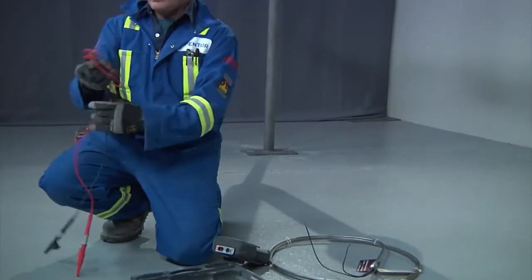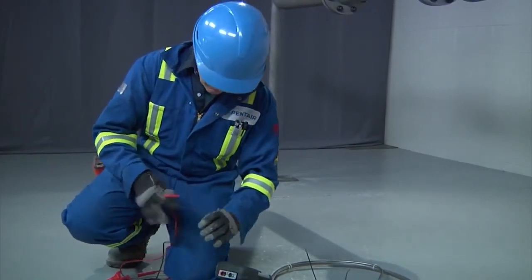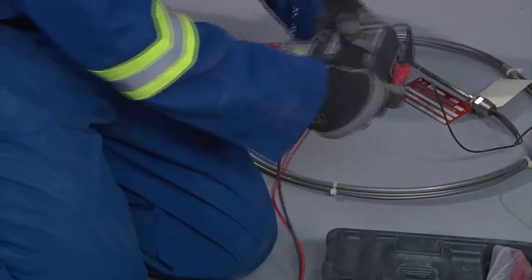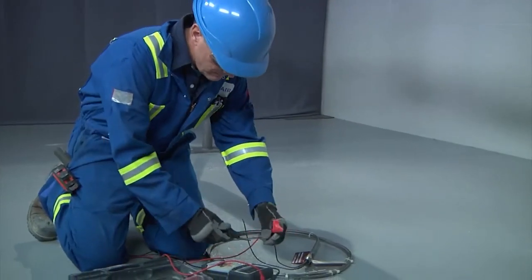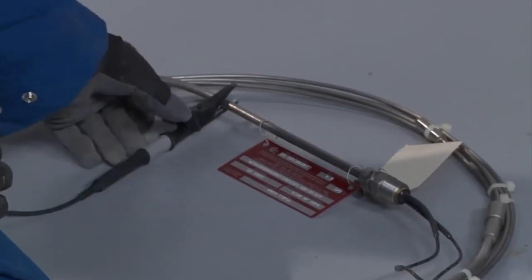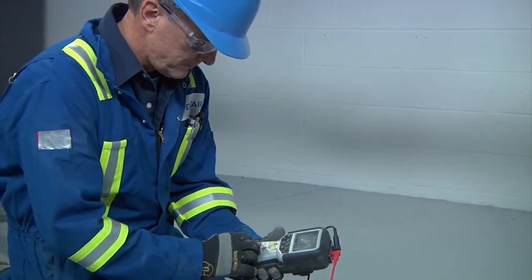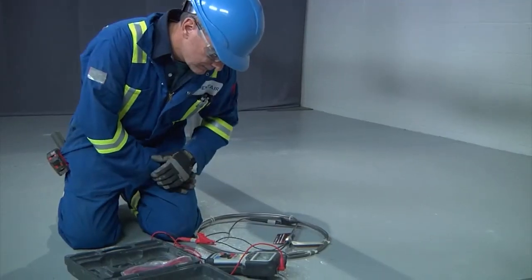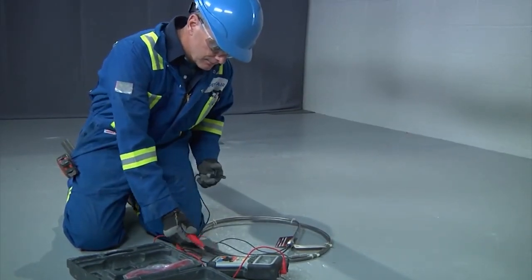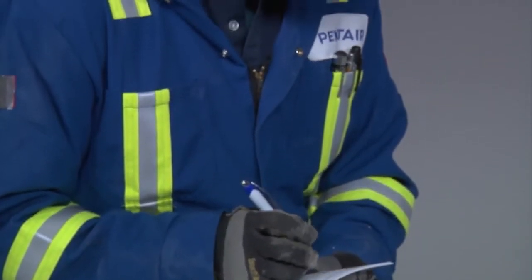Conduct an insulation resistance test while the cable is still coiled and in as-received condition out of the box. Measure the insulation resistance between the conductors and the cable sheath by connecting one megohmmeter lead to the conductors and the other lead to the cable sheath. The insulation resistance test should be conducted using a test voltage of 1000 volts DC; however, in the absence of equipment with this capability, a 500 volts DC test is suitable to detect most installation-related concerns. Insulation resistance should be 100 megohms minimum.